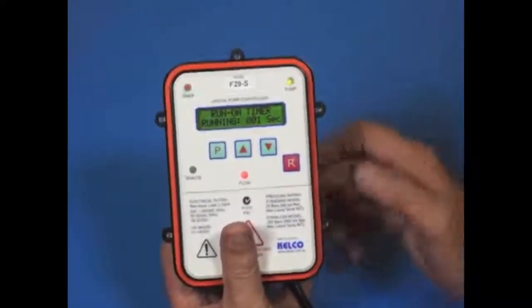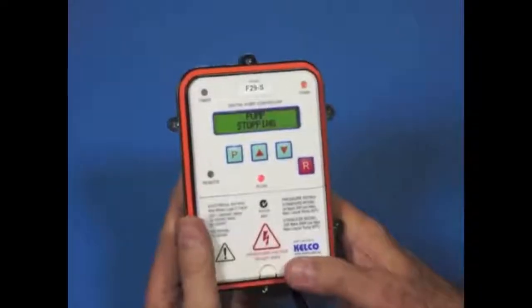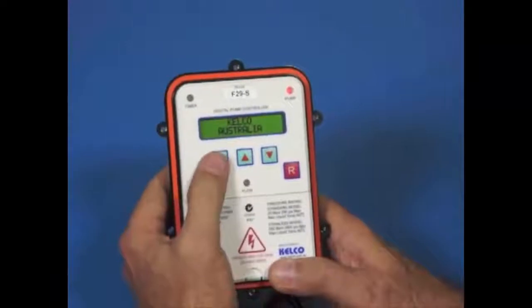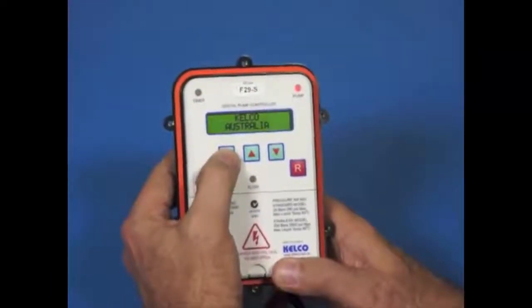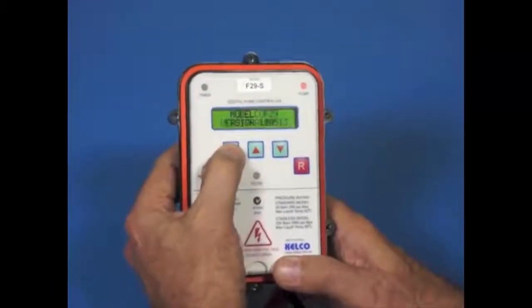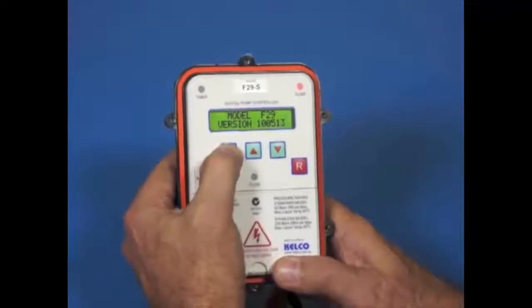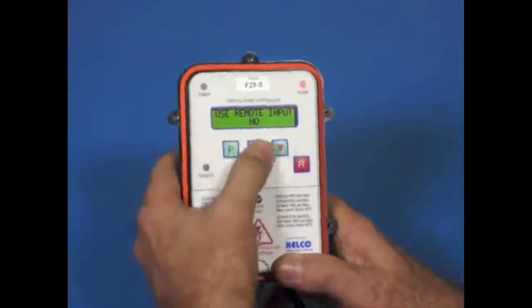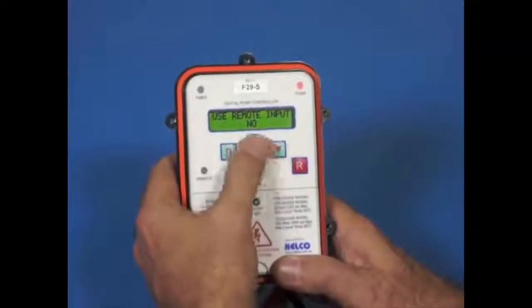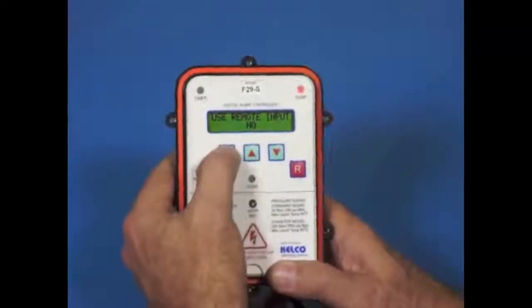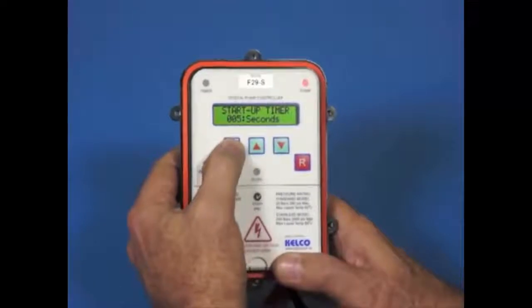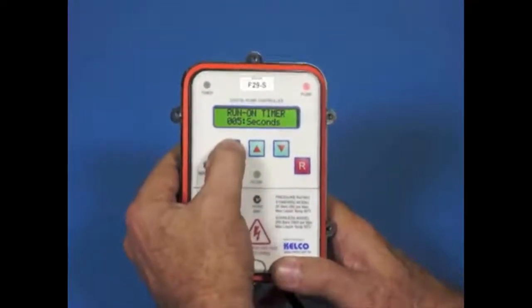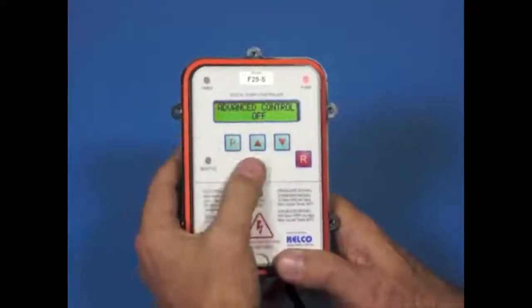If we want to change those settings here, all we do then is press the P button to enter programming, like that, and then press it again to step through the menu until we get to the parameter we want to change. So we just press it. It'll display the model number and the version. It'll ask us if we want to use a remote input. Using the up or down buttons here, let's just select yes or no to these questions as they come up. In this case, no. Our start-up timer there is set to five seconds. Our run-on is set to five seconds. There are the default settings. And the advanced controls are off. So we might turn the advanced controls on.